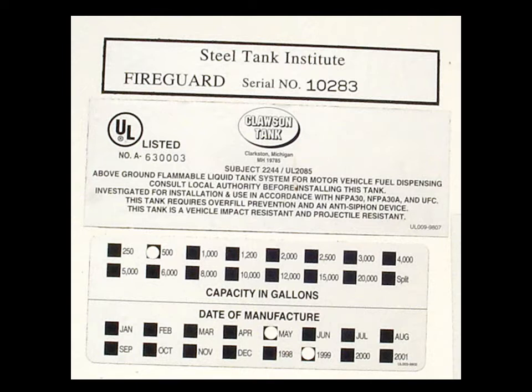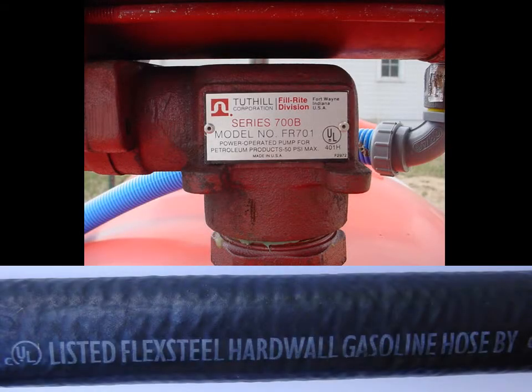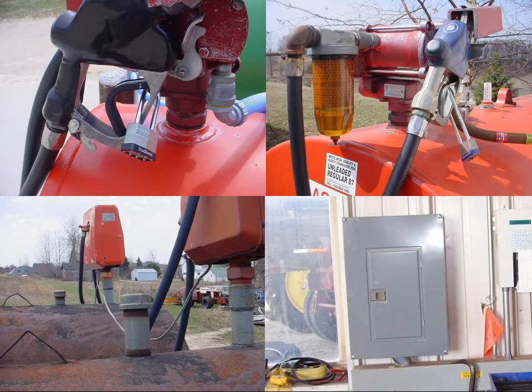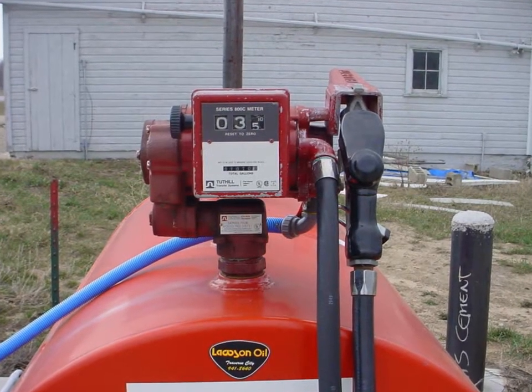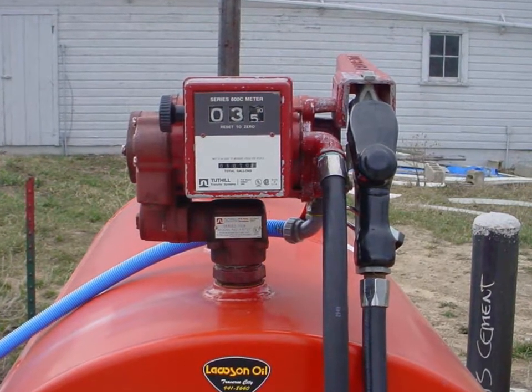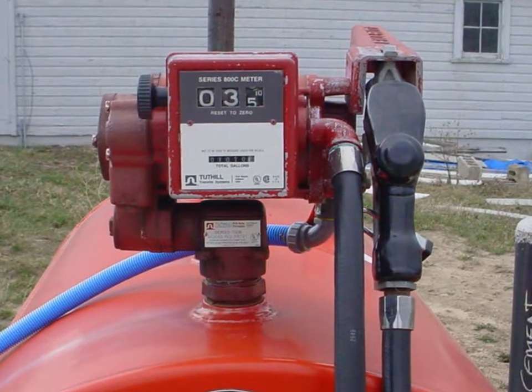This tank can be used within 10 feet of a building due to its higher fire protection rating. The tank must have a permanently attached pump and approved hose for the type of fuel on the top opening tank. In order to protect the environment and to prevent tampering which might lead to a fire hazard, owners are required to make dispensers inoperable. This can be done with a padlock or by using an electrical shutoff. The pump discharge must be equipped with an anti-siphoning device or the discharge hose must have a self-closing nozzle, providing protection from environmental contamination, fire hazard, and fuel loss.